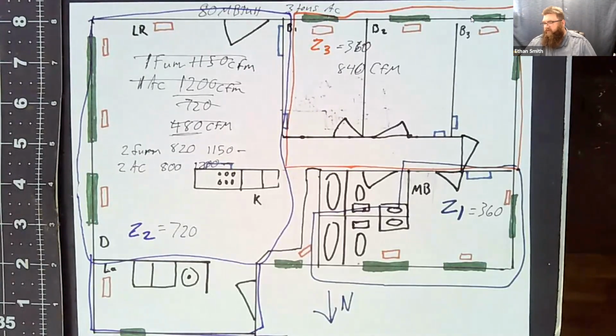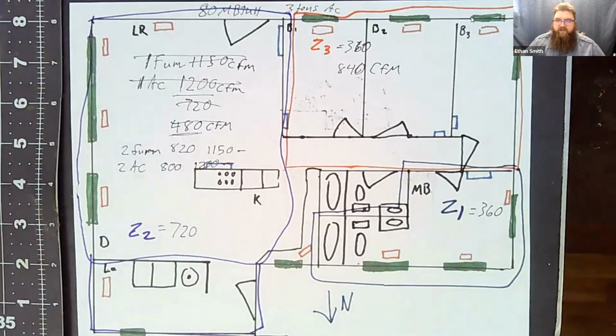It wouldn't be terribly ideal because anytime we're doing a dump or bypass, we're taking that efficiency factor and really flushing it down the toilet, or we're not saving them any money in that case. But I would venture to say that if you were to divide this house into two zones instead of three, a two-stage piece of equipment would work very well. Okay. Because in that two-stage furnace, we've got a blower that we're capable of turning down a little bit so that we would not have an excess air problem. So we wouldn't need a bypass and we wouldn't need a dump.